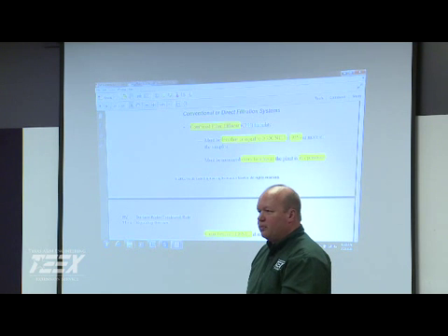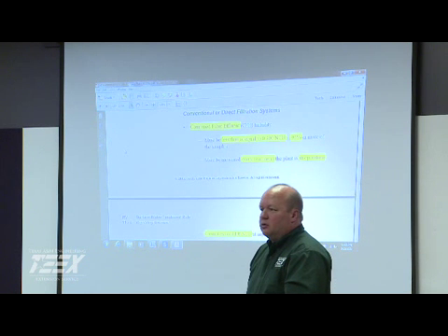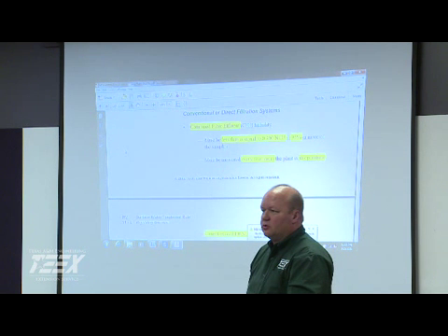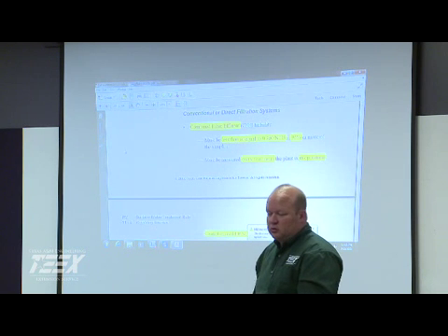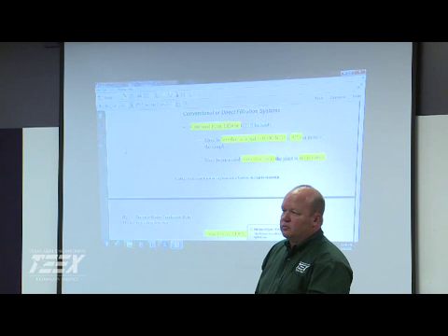Mm-hmm. Yeah, we made a change to our regulations back in 2008, I think, and kind of reversed it. Originally it was you grab sample every 4 hours. Then we reversed it to say you've got to continuously monitor, however, we can approve you to do grab sampling. So we've got a few systems like Rockwood, who does grab samples, and then they're also using the highest turbidimeter on their individual as combined filter effluent for the old side. It's the old side, right? The old side. So, yeah, we've made a change in our regulations. It's kind of different from EPA's.